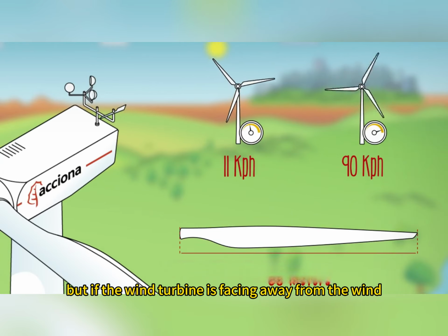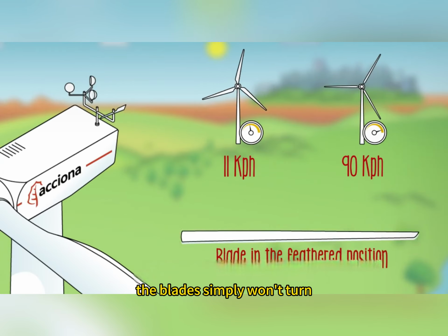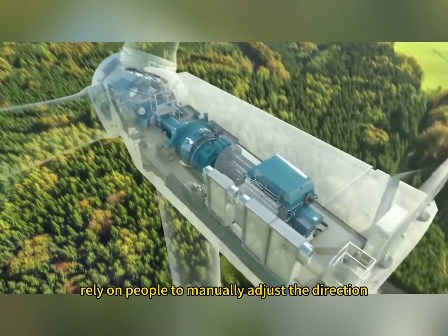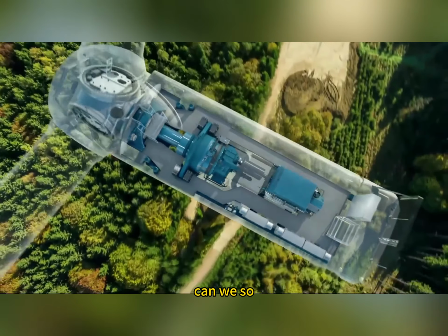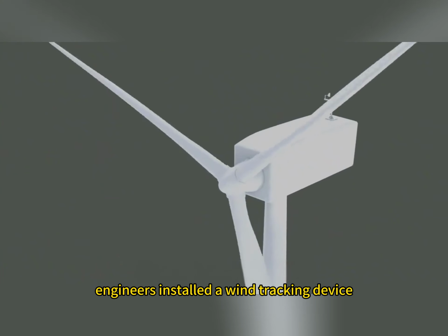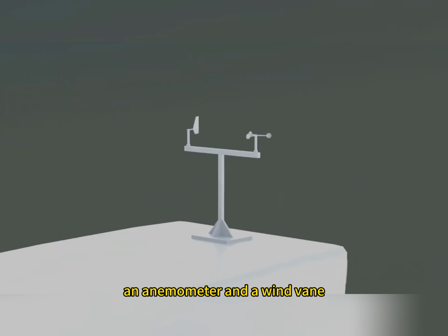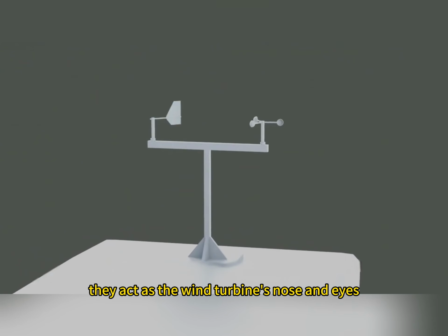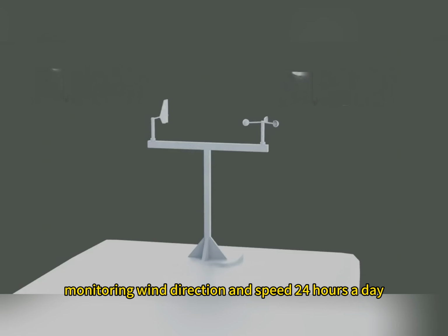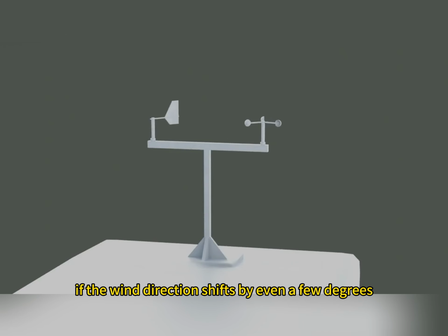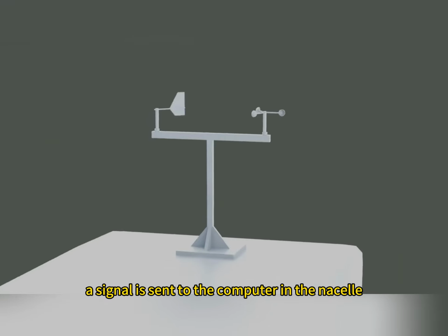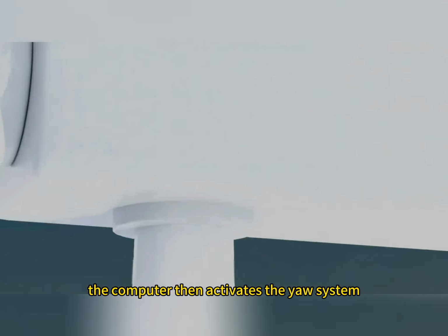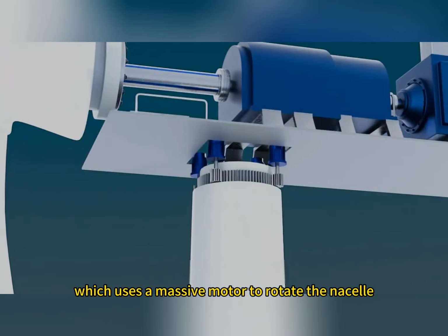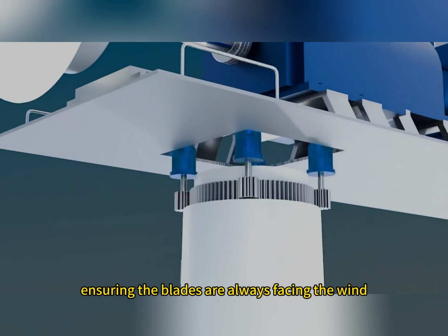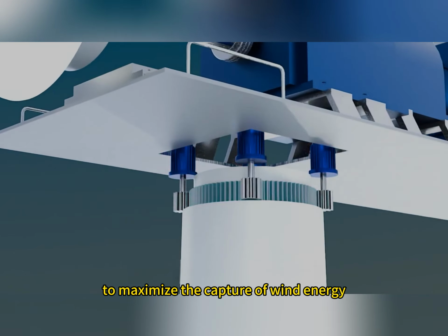But if the wind turbine is facing away from the wind, the blades simply won't turn. We can't very well rely on people to manually adjust the direction, can we? So engineers installed a wind tracking device at the rear of the nacelle, an anemometer and a wind vane. They act as the wind turbine's nose and eyes, monitoring wind direction and speed 24 hours a day. If the wind direction shifts by even a few degrees, a signal is sent to the computer in the nacelle. The computer then activates the yaw system, which uses a massive motor to rotate the nacelle, ensuring the blades are always facing the wind to maximize the capture of wind energy.